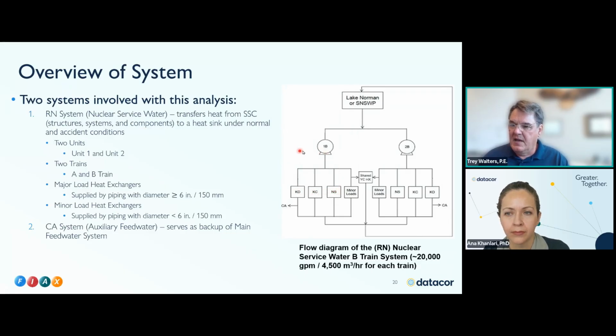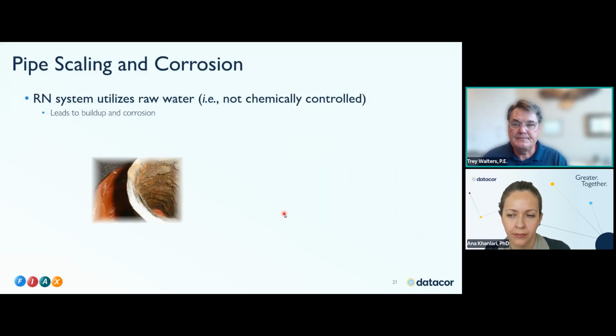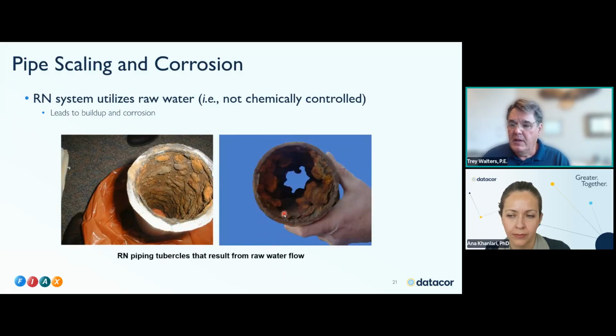This is the 1B, the B train going to the Unit 1, and then another independent one going to Unit 2, and then they could cross over if they needed to. And then they had a bunch of minor load heat exchangers. And then they had these CA systems, and these were the ones that made for the main backup to the primary cooling systems for the reactors. So because they were pulling water out of Lake Norman, these are actual pipes that they pulled out of their operations and took photos of.